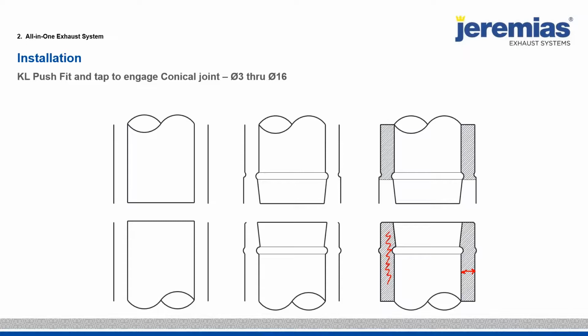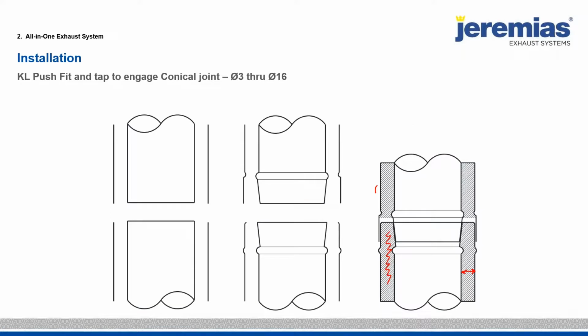The one side of it is expanded right here. So when you push the systems together, you still have flashing going down. So rainwater outdoors, again, no sort of silicone or anything like that's required. And then you add an outer band to hold the outer jacket in place. So again, this is a very unique system. What's great about this is that using this insulation means that we have no brackets, no spot welding. I can actually sell this fiber insulated stack system for less cost than our own airspace systems. So basically you get this fiber insulation for free.